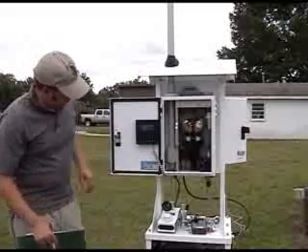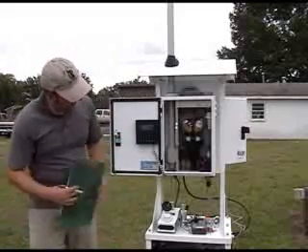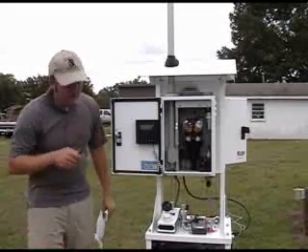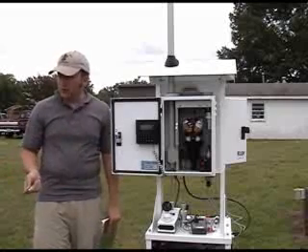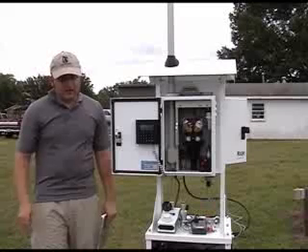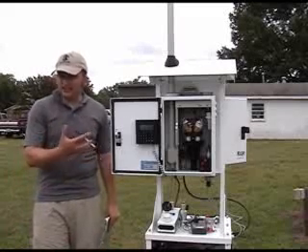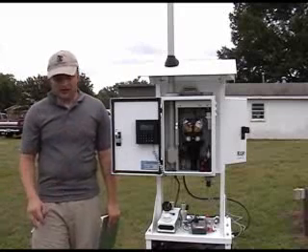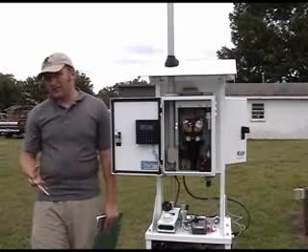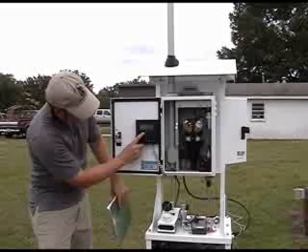So, number of modules, like I said before, we've only got one module. This isn't a co-located site. Enter. Next is our schedule. We do 1 in 3, 1 in 6, or that improved protocol where it would sequentially sample through the filters. So this instrument does support that method, but it requires RTI to send you a cassette that's set up with those filters. But the improved method is for 1 in 3, so this site will never likely make use of that because we're 1 in 6. So that's option number 2, 1 in 6.